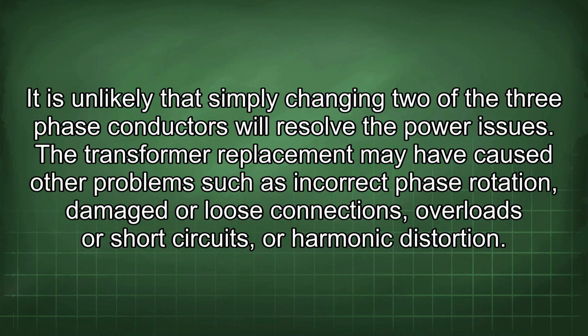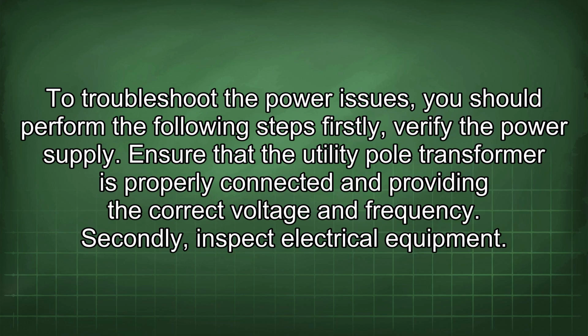It is unlikely that simply changing two of the three-phase conductors will resolve the power issues. The transformer replacement may have caused other problems such as incorrect phase rotation, damaged or loose connections, overloads or short circuits, or harmonic distortion. To troubleshoot the power issues, you should perform the following steps.